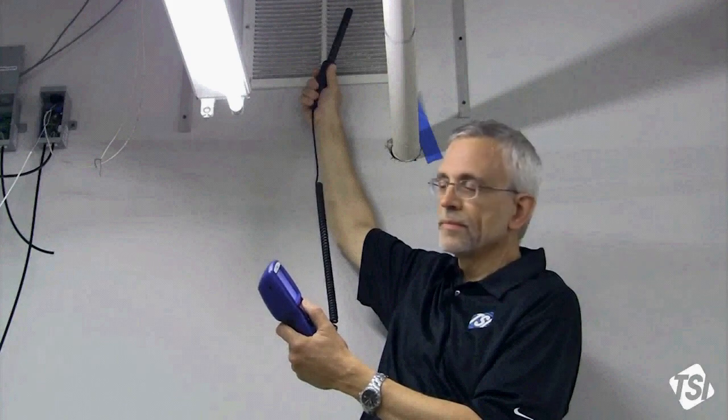This calculation can now be used to calculate the volume of outside air per person. You can then compare that value to the table in ASHRAE Standard 62 to determine if an adequate amount of outside air per person is being supplied for a particular space or building.